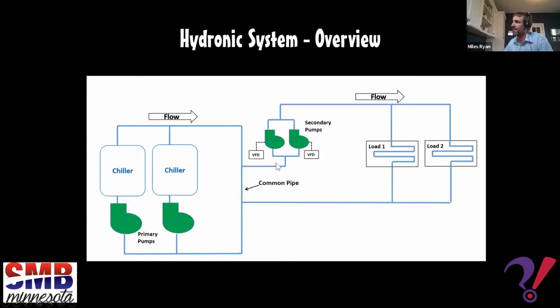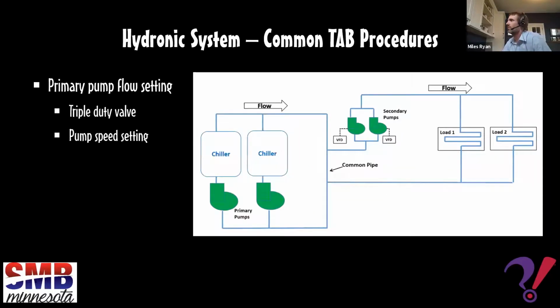Okay, the secondary pumps though are a little bit different. They operate kind of like what I was talking about before. They're going to slow down and speed up to maintain a differential pressure set point somewhere out in the system, measured across the loads out there. All right, so let's talk about what the TAB professional does to make sure that the primary pumps associated with the chiller in this case are meeting their design flow requirements?